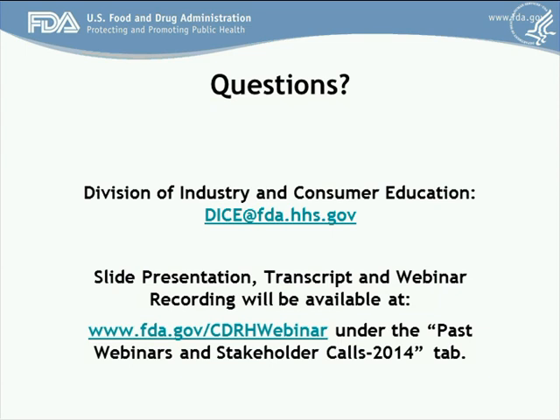Thank you. Our next question is from Dan Schmidt. Your line is open. Thank you. So the FDA guidance emphasizes limiting user access and password strength requirements. If that responsibility is moved over to the health system through, as an example, Active Directory integration, is that considered a preferred solution, essentially moving that responsibility to the health system rather than building it into the medical device solution? Again, that is a recommendation. If there's an alternative, including moving it, as you suggested, that would mitigate the risk adequately, I think this would be one we'd consider. I would not want to be prescriptive now and say that was something that you should do. Again, what we'd like to see is threats posed by simple passwords or easy authentication be limited. Okay, thank you.